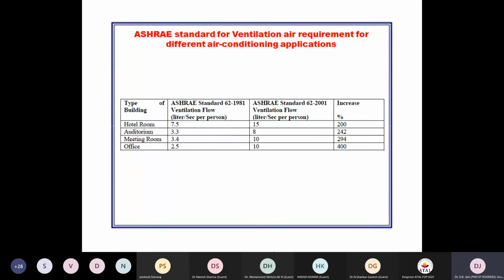The ASHRAE standard requires not just cooling air temperature. Normally in air conditioning, the temperature is controlled at 25 degrees centigrade and the humidity at 50%. A number of experiments conducted by various scientists and researchers previously led to that value. It is universally accepted for different continents and different peoples; it is a very generalized value. To maintain the air quality index, we have to provide oxygen, so there must always be ventilation airflow.